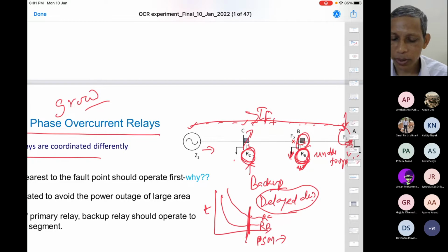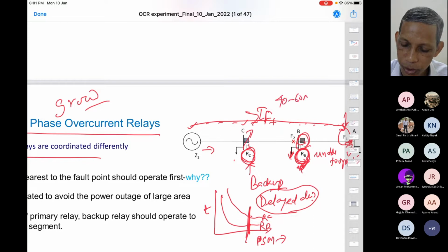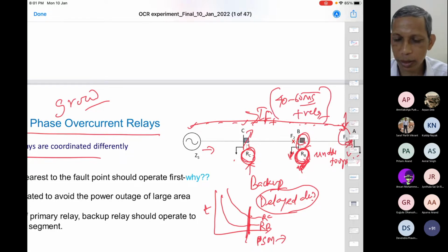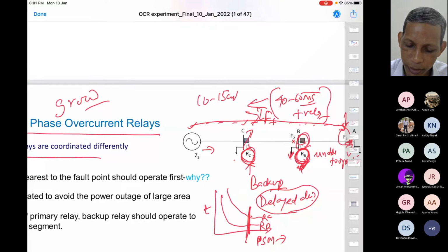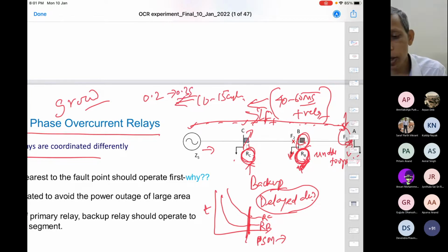Wait and watch. How much time? Typically, what is being done is that RB takes its own decision time plus the breaker opening time. The breaker opening time, we can say typically 2 cycles, 3 cycles, so 40, 50, 60 milliseconds, typically, not necessarily minimum, plus the relay decision time. Commonly all this arrangement and all uncertainties are taken care of. So typically 10 to 15 cycles are given, and this is nothing but 0.2 to 0.3 seconds. So after a delay of 0.2 to 0.3 seconds, because of the breaker and all operations here, this relay should operate. This relay should command the breaker to open. Is it clear? So this gap is the coordination time we call between relay RB and RC.